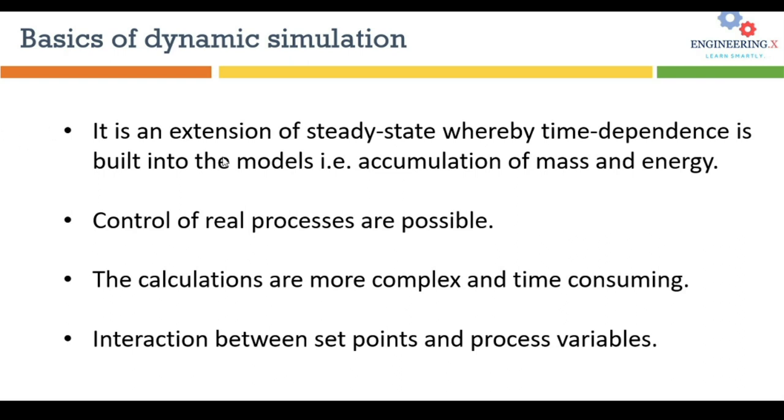Another thing is that the calculations in dynamic mode are way more complex and time consuming because of the dependency on the time interval. Actually, you are repeating the steady state simulation. For example, if the time interval is 1 second, you repeat all the calculations for each 1 second passing. So with time, all parameters are continuously changing in dynamic simulation, and this condition usually happens in process plants during the startup and shutdown operations.